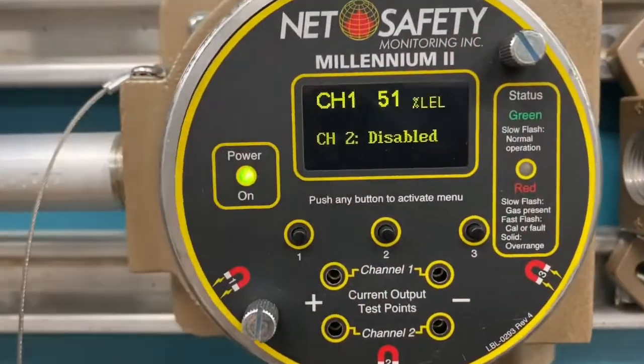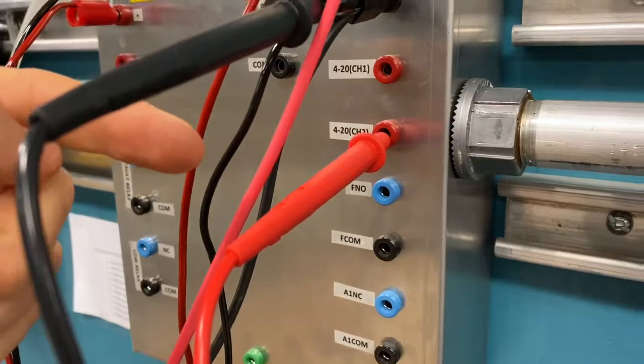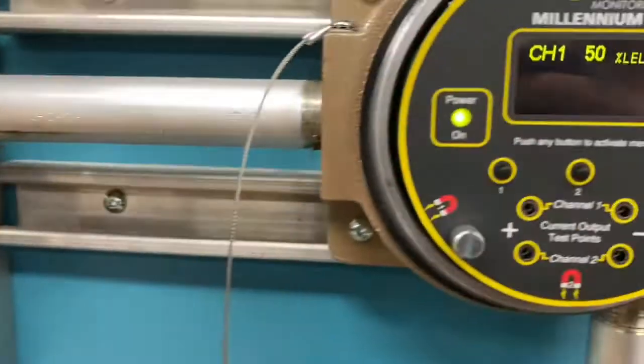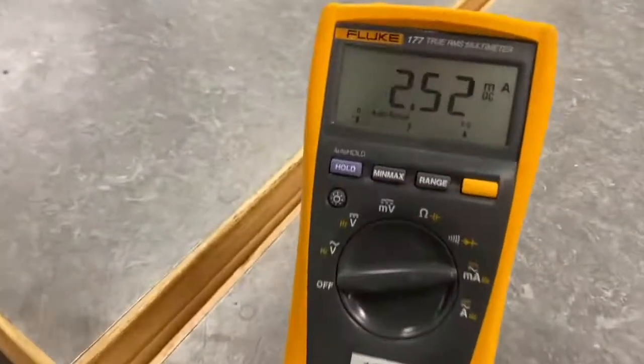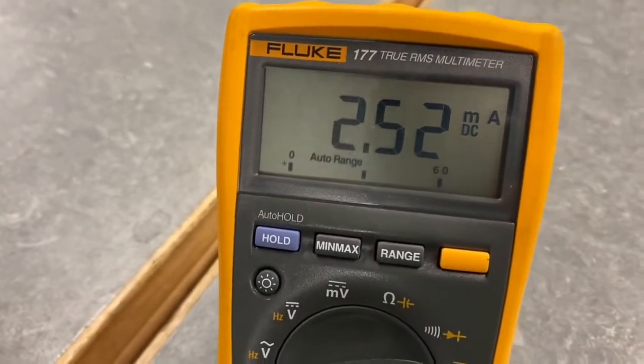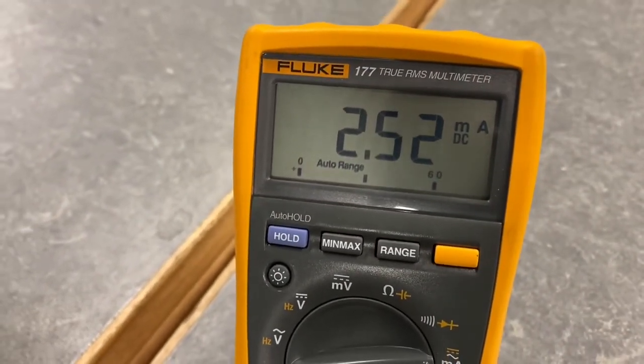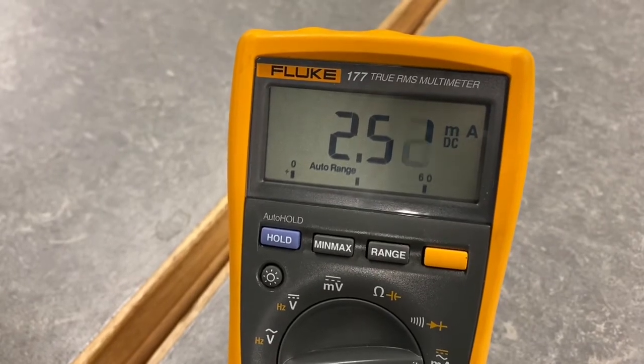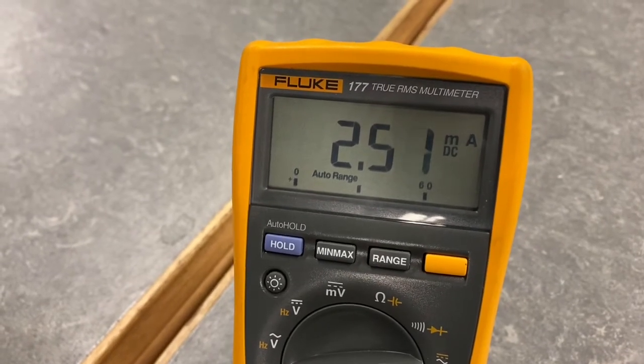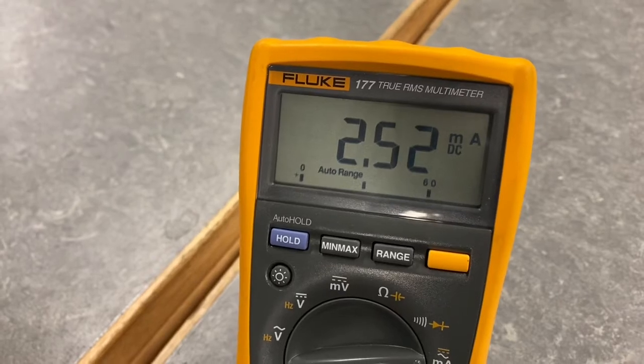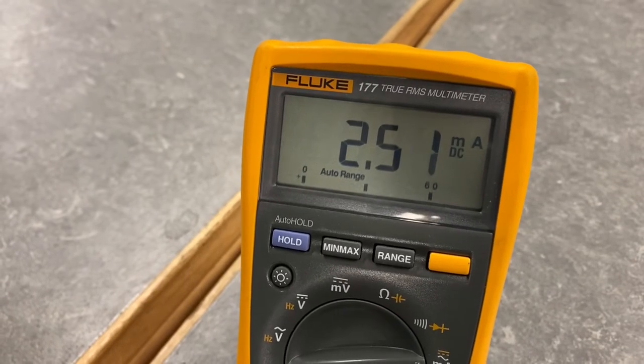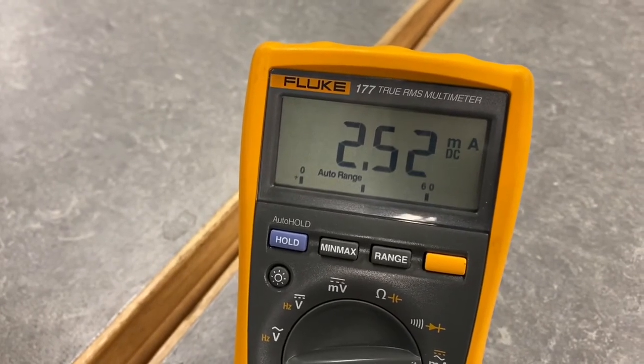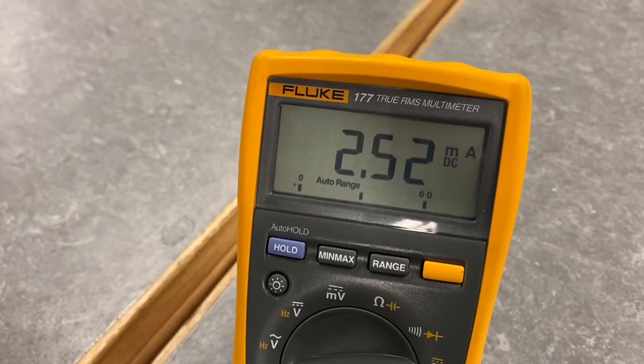The next thing I wanted to show you is I'm going to take a reading off of channel 2 and see what we get. All right, I moved my lead down to channel 2. You can see the red lead, and it's reading 2.52 milliamps. So what I'm going to get you to do, we're going to answer this question too. We're going to figure out what 2.52 milliamps means by looking up in the manual what 2.5 milliamps means when the controller is outputting that signal on that channel.